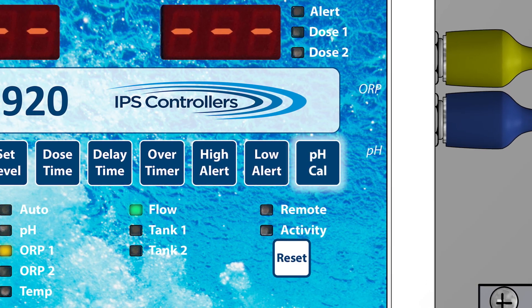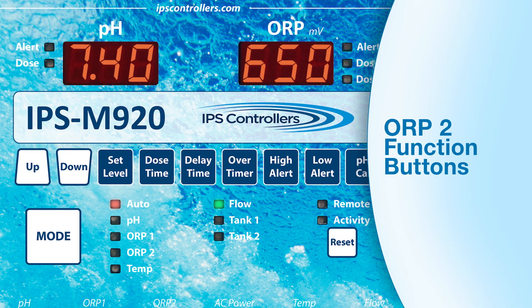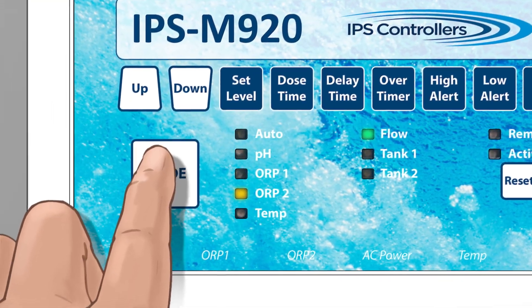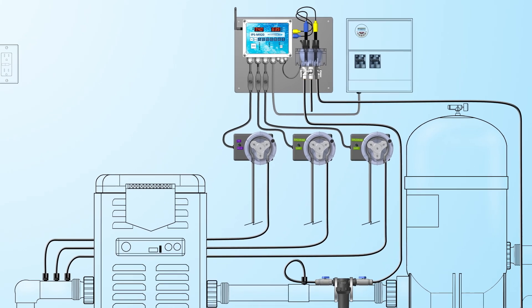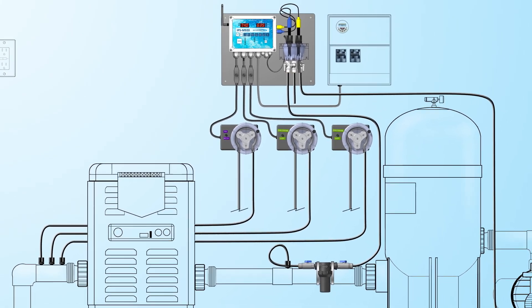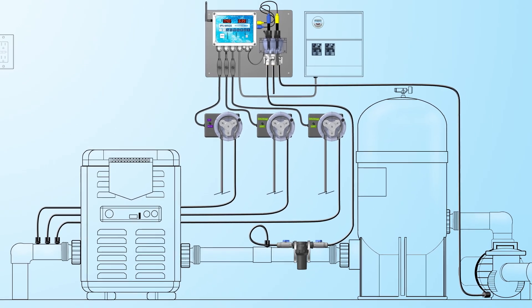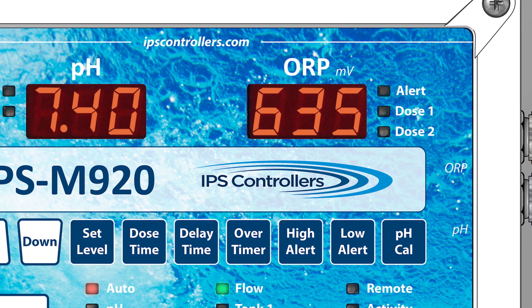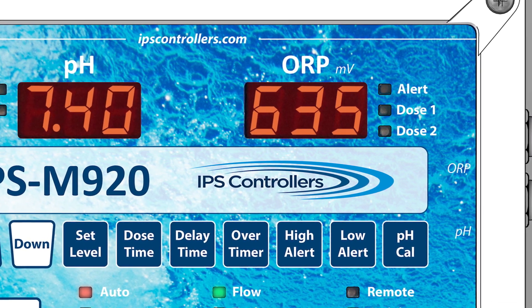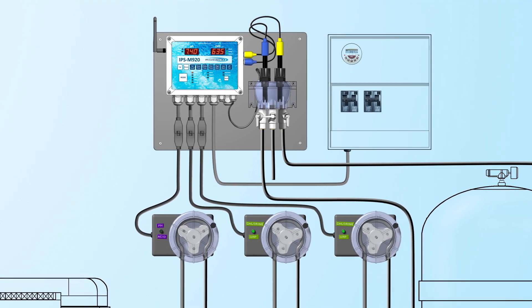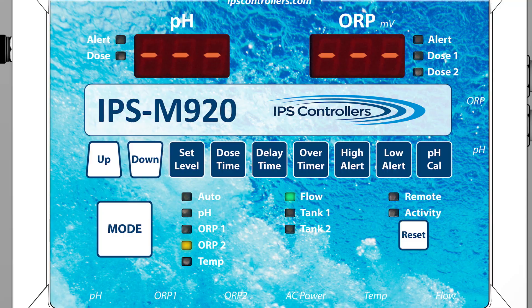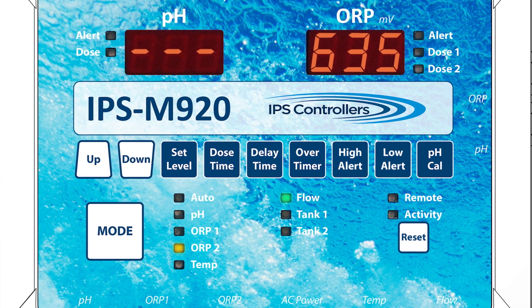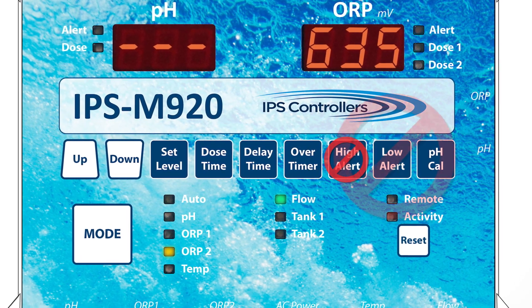The pH Cal button is disabled in the ORP mode. The ORP2 mode allows a second ORP pump to be added to the system. The additional pump supplements the sanitizer feed if ORP1 cannot maintain the correct ORP level. This can occur with an extremely high bather load, especially in the case of a salt system, which needs extra time to recover to the correct ORP level. The ORP2 pump runs in conjunction with the ORP1 pump. The ORP2 set level cannot exceed 10 millivolts less than the set level of ORP1. The ORP2 functions operate the same way as ORP1; however, the high and low alerts are determined by the ORP1 settings.